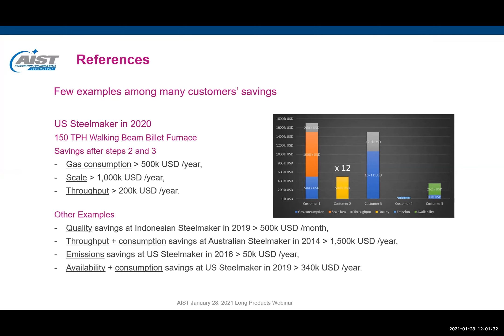No, so for this system, if you have the oxygen analyzer in the correct position in the furnace, and if the information is correct, we can do the control. We can use this to control the air pressure in order to ensure the air pressure and the oxygen content in the furnace is not too high. But only in case we can ensure the oxygen analyzer is very well calibrated, and also the information coming from, and the position of, the oxygen analyzer is good enough.